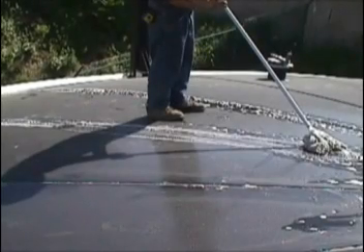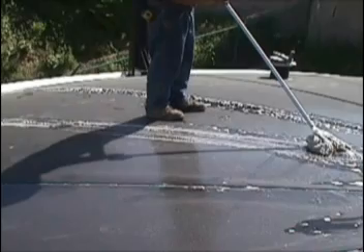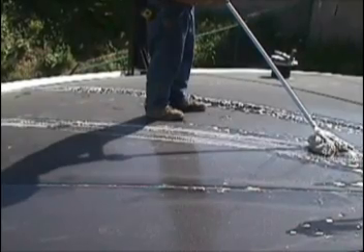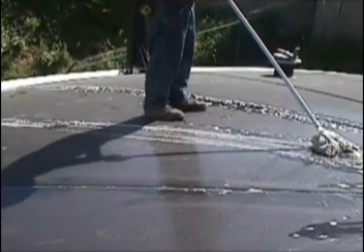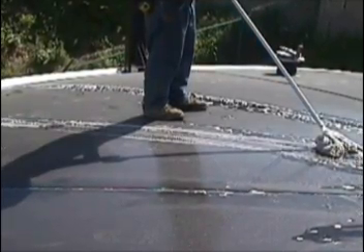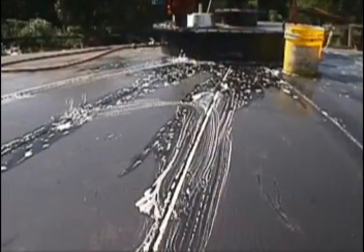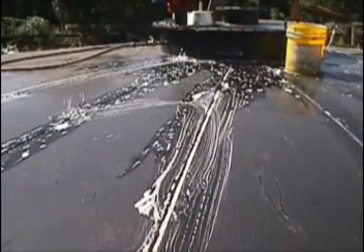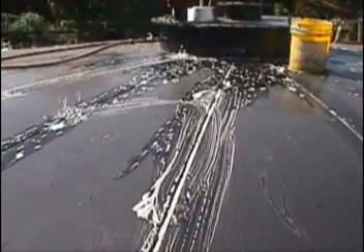Number twelve, weld testing. While the cover is floating, the welds can be tested using a soap and water solution. The solution can be applied using a mop and bucket or pressure sprayer. Look for leaks on each gas-tight weld and re-weld where necessary.